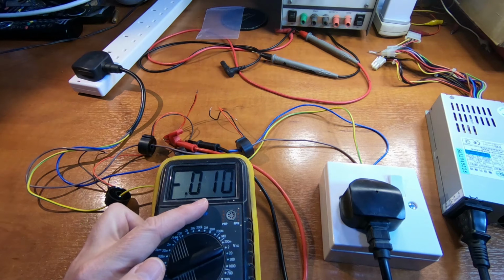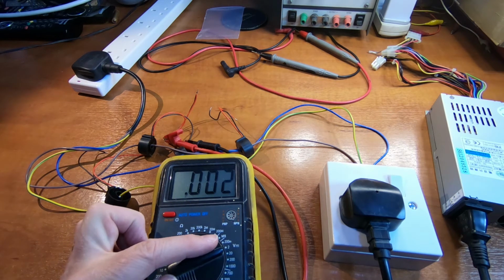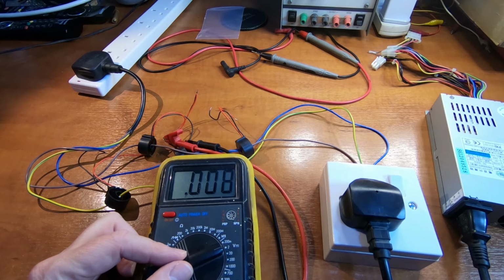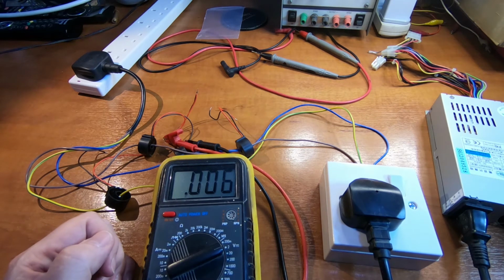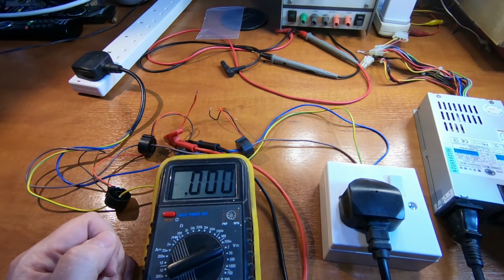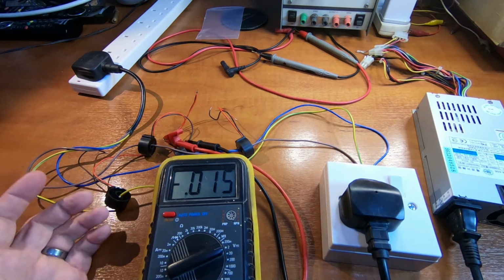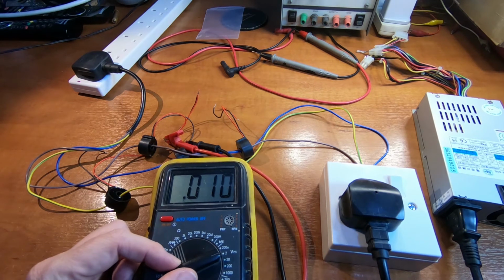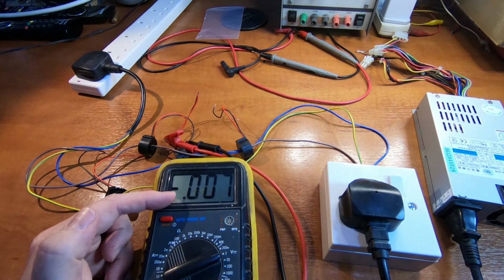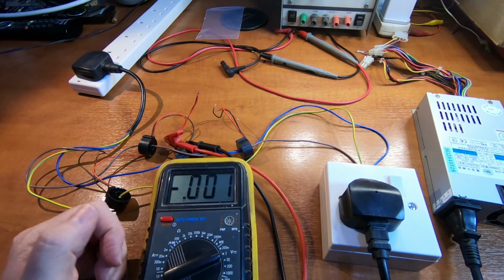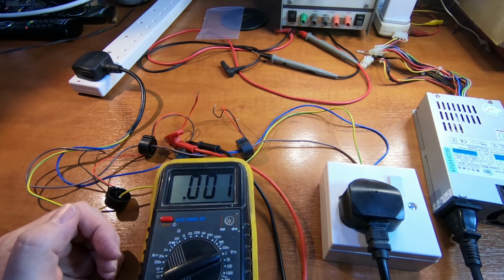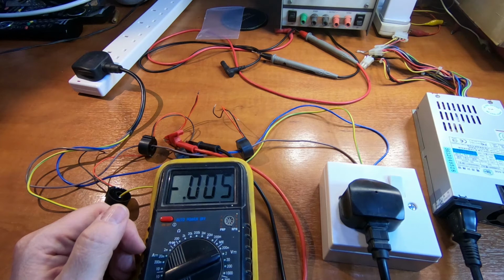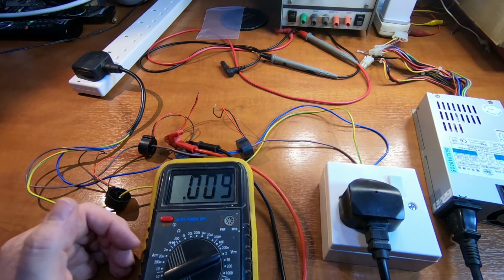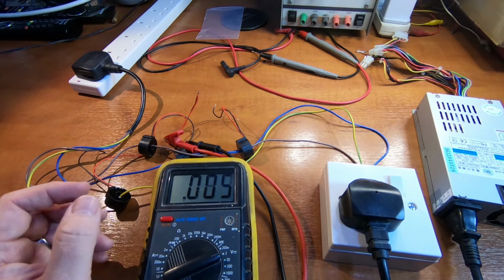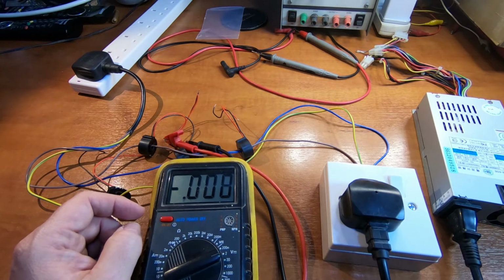Yeah, it's peaking over 200 millivolts, which is why it's going over range. It's fluctuating quite a lot. I expect that's because of the electronics in here, but that shouldn't affect our end product. It doesn't matter really what current is being drawn by the load - the earth leakage is all we're interested in. If it's drawing 13 amps or half an amp, doesn't matter. It's the earth leakage amount we're concerned about.